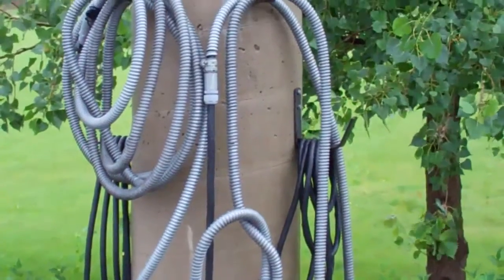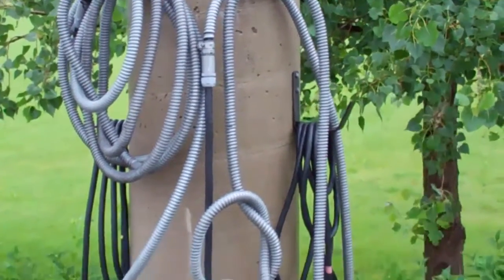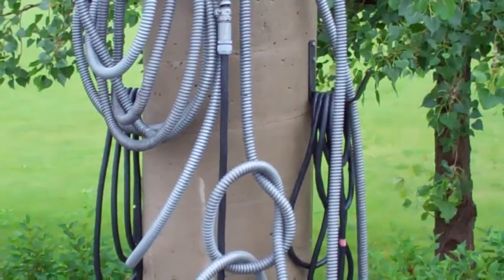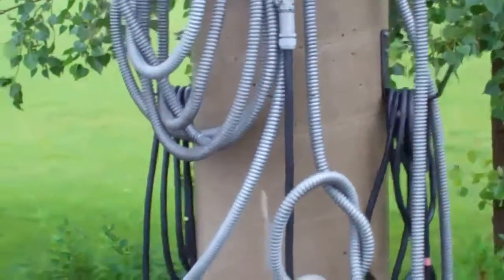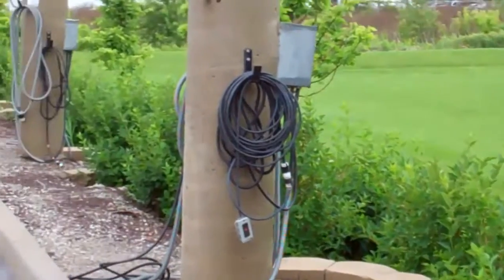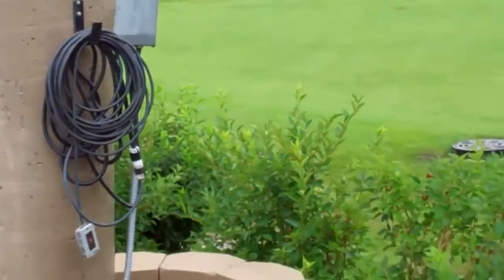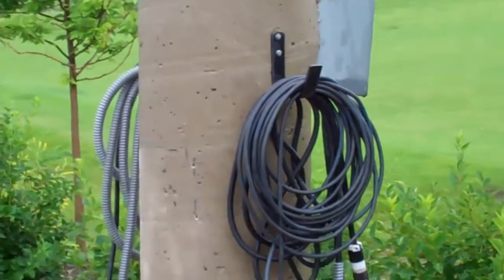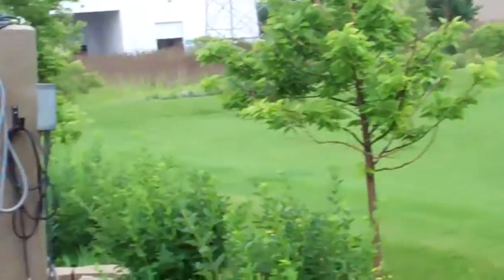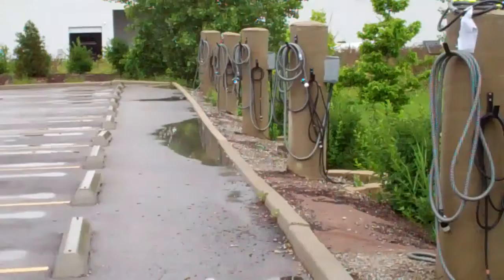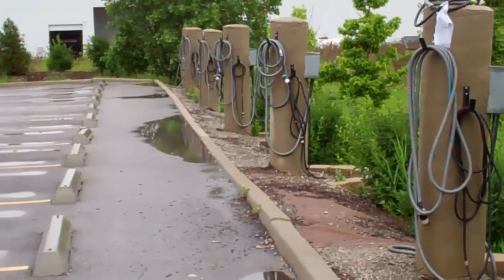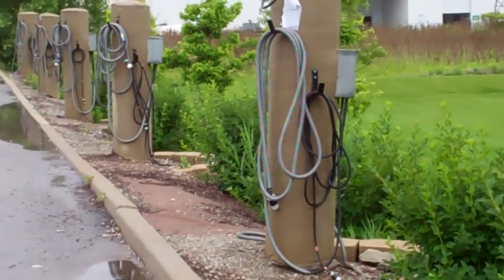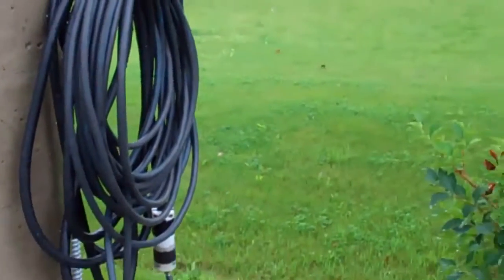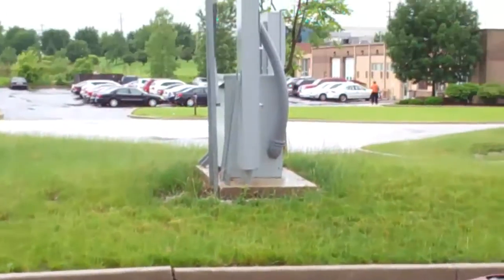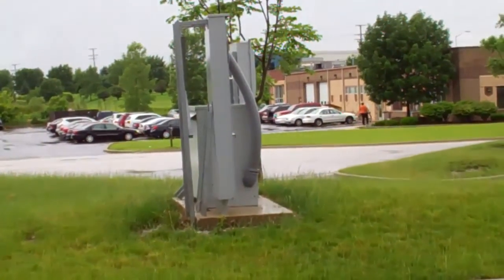Another thing you can see is there's no disconnect switches on any of these cords. However, the electrical code doesn't say at this point you need to have disconnect switches at these posts, and you can see we have something like 15 spots going down this lot. The reason being, the code says that you can use a circuit breaker to de-energize this power cord as long as the circuit breaker panel is within sight of the plug.